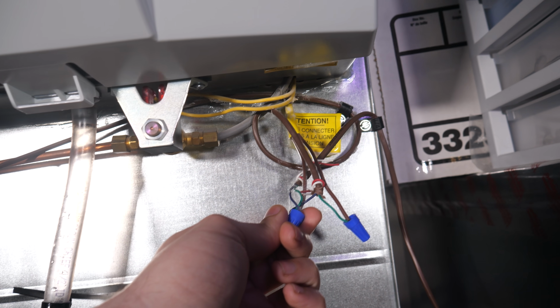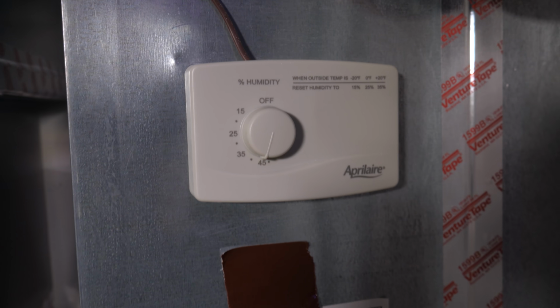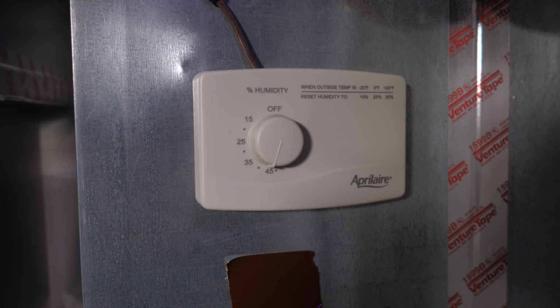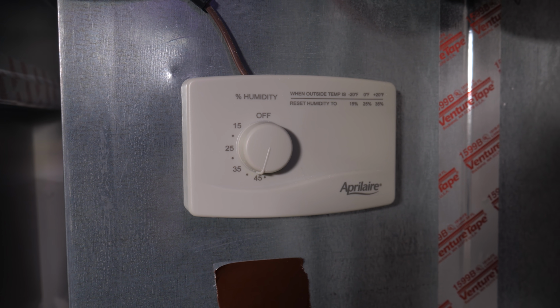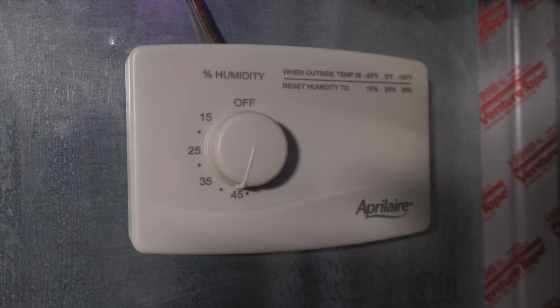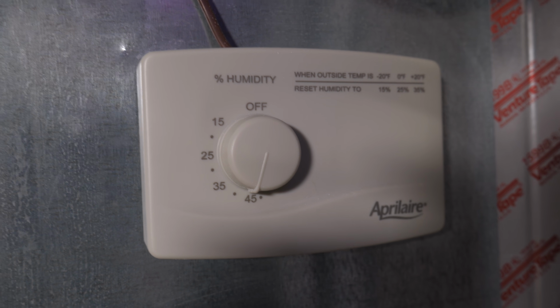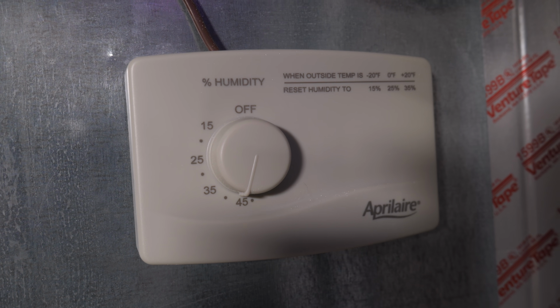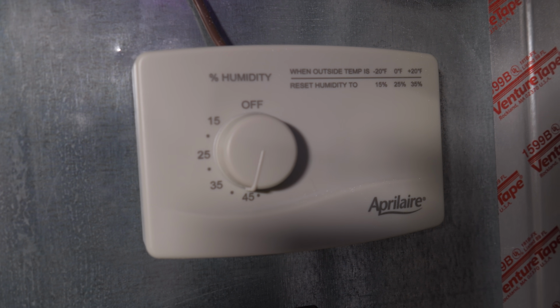But the humidifier can't simply run whenever the heat's on. That would likely result in over-humidification, which could be uncomfortable or even cause mold issues. So rather than hook the water valve to the furnace directly, its power wire goes through this humidistat. This is a fully analog doodad which sits in the return airstream and closes a switch when the humidity is lower than your desired set point. So long as that switch is closed and the thermostat is calling for heat, then the humidifier will run. But once the humidifier has elevated humidity to your set point, that switch will open and the humidifier will shut off, even if the heat is still running. It's a very simple control setup, but it works great. Except for when it doesn't.